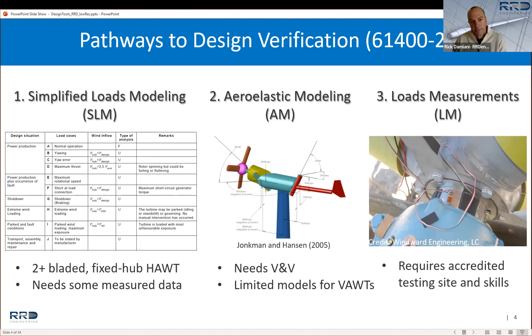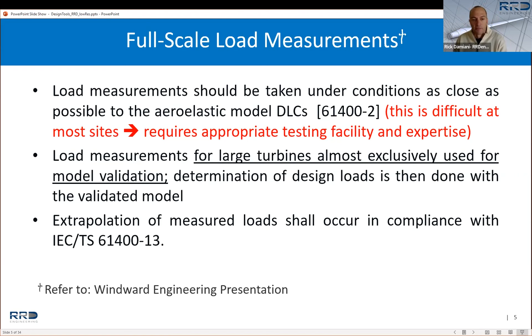Just a couple of words about full-scale measurements. Referring back to what Dean talked about in his previous presentation, I want to highlight that the standard requires load measurements be taken under conditions as close as possible to the aeroelastic model DLCs. This statement is actually quite difficult to achieve at most sites. It requires appropriate testing facilities with inflow of a certain quality, and the expertise Dean described for load extrapolation and arriving at design loads from measurements. As a term of reference, utility scale turbines use load measurements exclusively for model validation, but design loads are really extracted from validated models.